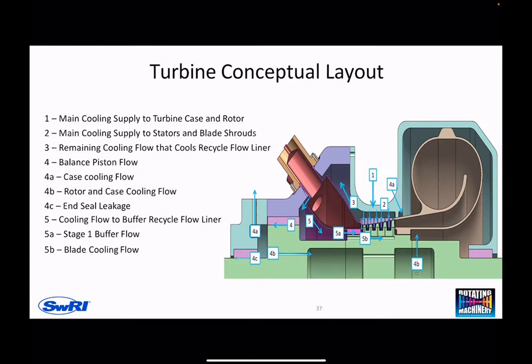So mainly we have the main flow coming into the turbine at zone one. At zone two, you're supplying the stator vanes. These stator vanes are still very, very hot, with the first stage stator seeing the highest temperature and pressure combination in the entire system at around 1200 C and 305 bar.